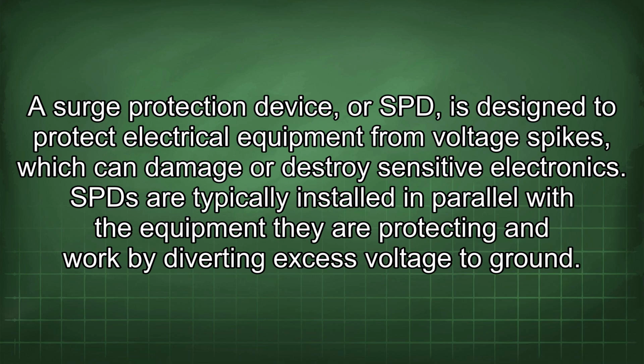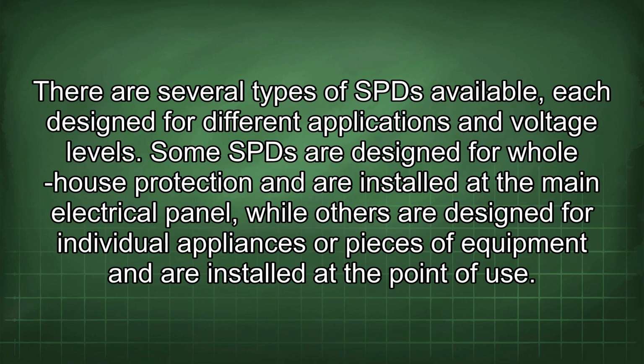A surge protection device, or SPD, is designed to protect electrical equipment from voltage spikes, which can damage or destroy sensitive electronics. SPD are typically installed in parallel with the equipment they are protecting and work by diverting excess voltage to ground. There are several types of SPD available, each designed for different applications and voltage levels. Some SPD are designed for whole house protection and are installed at the main electrical panel, while others are designed for individual appliances or pieces of equipment and are installed at the point of use.